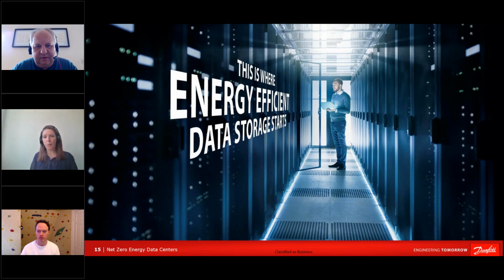Yeah, maybe Jakob, would you talk a little bit about the DC solutions with our drives? Thank you. And I can mention that we are looking into using direct current as solutions for data centers too. One of the big advantages to shift to DC, which we, for the record, have experience with from marine industry. So it's not just something we're saying, but one of the big advantages is we can remove power conversion steps, which will save energy, but also save on the heat generation side. So we have seen reports that say if you could go to all DC power distribution in data centers, you could actually save as much as 10 to 15% on the data center itself. So it's one area we're exploring, and it's one area we happily take inputs and discussions on too.